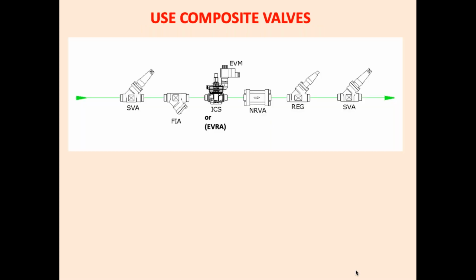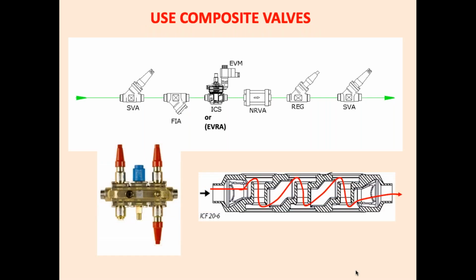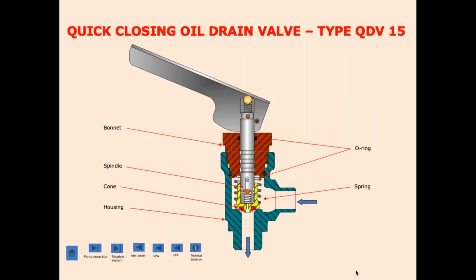This is my experience. Use composite valves like this. This is a composite valve, and the pressure drops are low, welding joints are low, everything is useful. Then for oil draining, I did mention to you, use a quick drain closing valve. This is a quick drain closing valve. It is spring loaded with a handle. So when you keep the handle pressed, the valve is open. If by accident a lot of liquid is coming and you want to stop, just release your hand, and the ammonia removal, oil removal will be stopped. So this quick closing oil drain valve is very, very important.